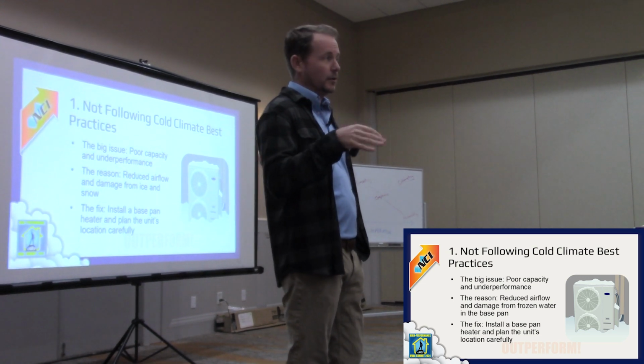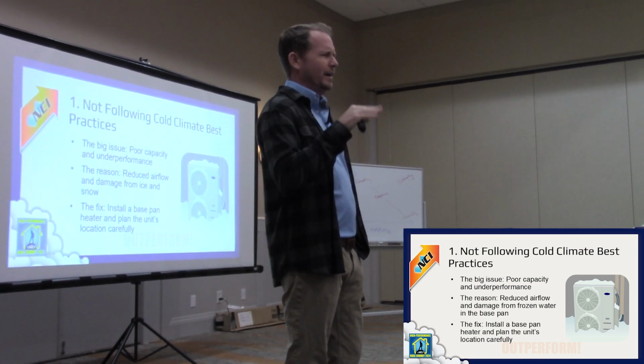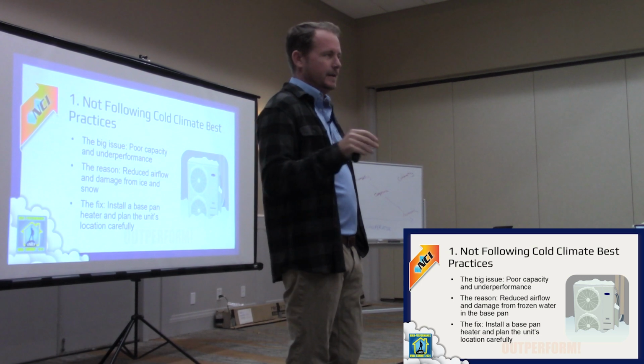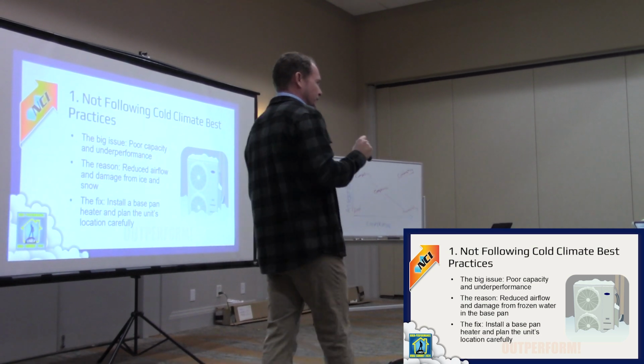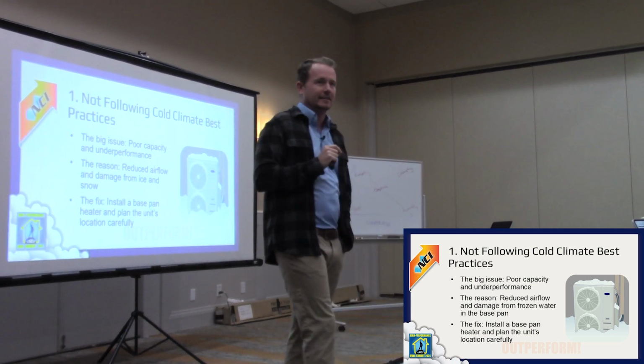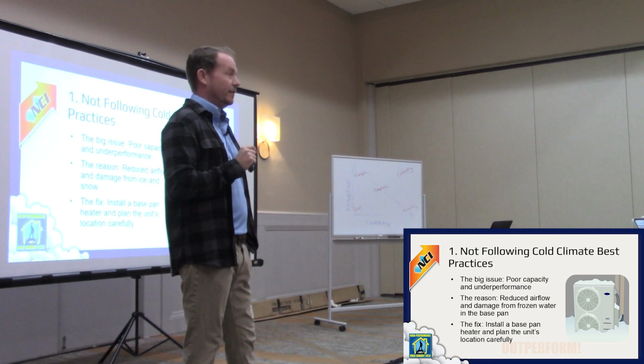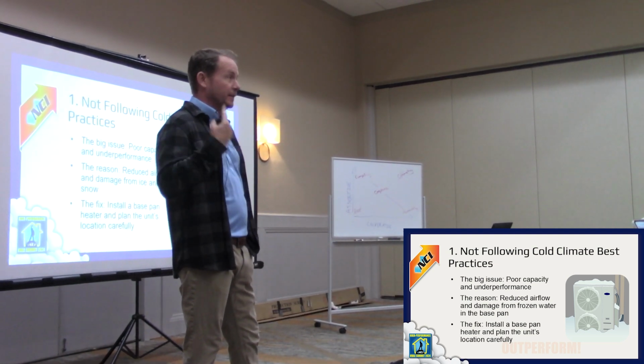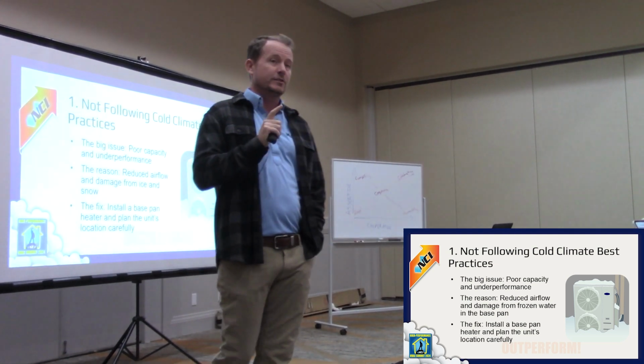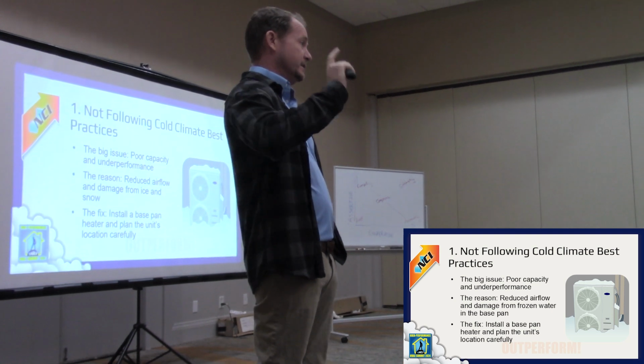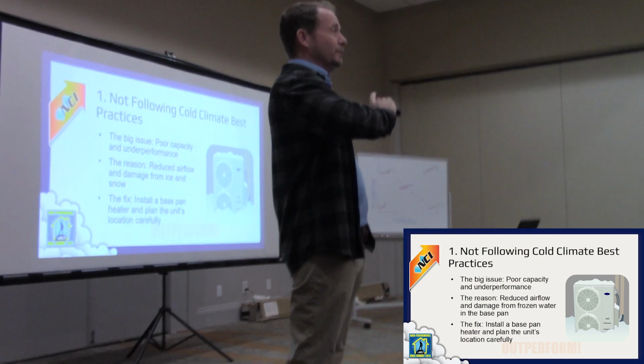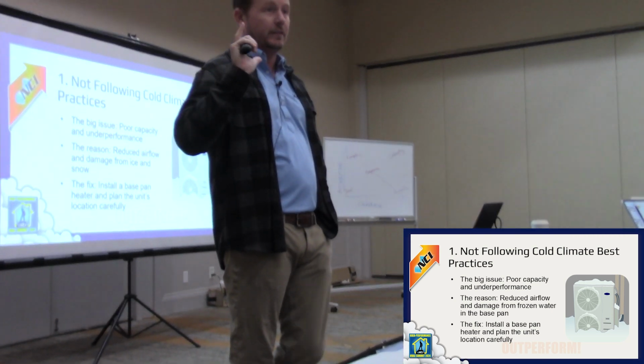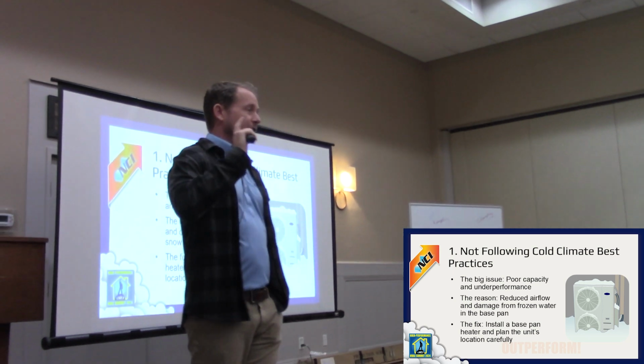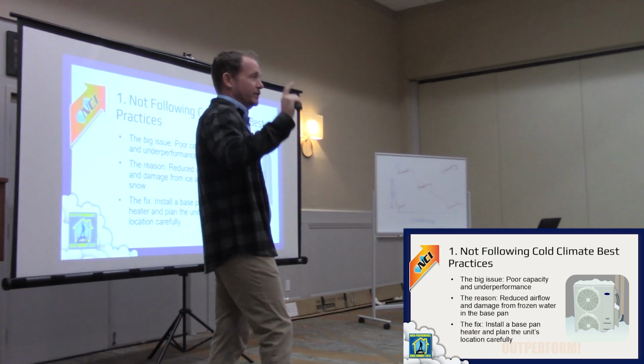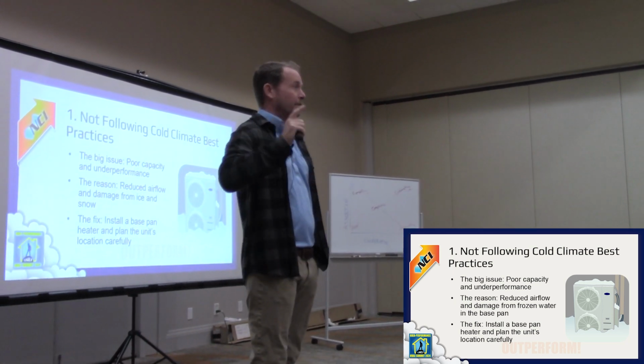A lot of people will say, well, inverter driven, they're amazingly quiet, phenomenally quiet. You go to it in the middle of summer once it's already at set point, oh man, they're so quiet. You go back in the middle of winter when it's negative 10 degrees outside and it sounds like it's screaming its head off, because what's it doing? Spinning the compressor faster. We're so used to things that operate on 60 hertz, and there's all kinds of weird stuff that happens when you start changing the frequency — weird resonant frequencies, weird noises, and you can't get rid of it.